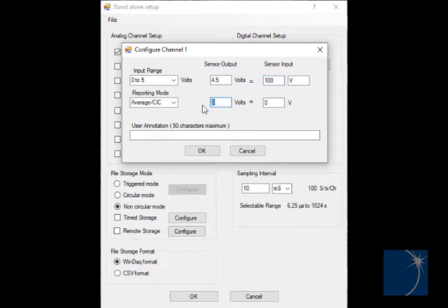Next, we'll scale the 0.5 to 4.5 volt output of the pressure transducer into PSI. So 4.5 volts equals 100, 0.5 volts equals 0.